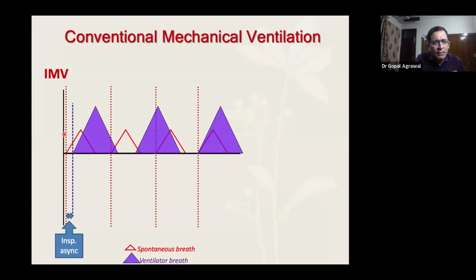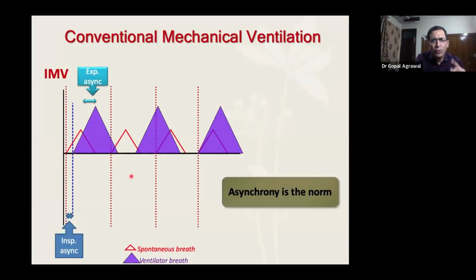So if you see, the baby has started breathing, the machine then starts giving its inspiration, and there's a gap between the inspiration of the baby and the machine. That's called inspiratory asynchrony. There is no synchrony between the baby's and the machine's inspiratory cycle. At the same time, the baby has started breathing out, but the machine is actually giving inspiration. So there is expiratory asynchrony. So there are two types of asynchrony here. Inspiratory asynchrony, where the baby is midway through its inspiration and then the machine starts giving inspiration. And the baby has started expiration, but the machine is giving its breath. So this is expiratory asynchrony. So the basic problem with intermittent mandatory ventilation is asynchrony, both inspiratory and expiratory. So why are we worried about asynchrony?